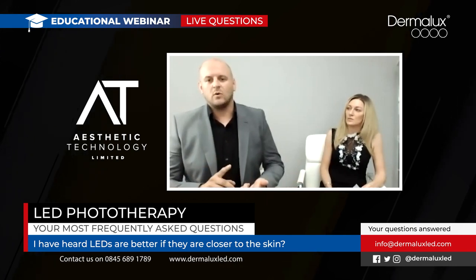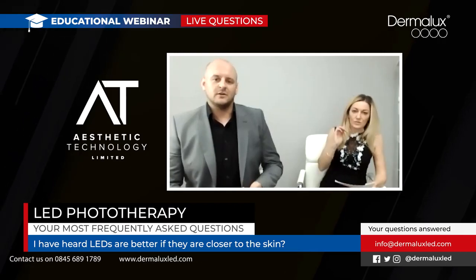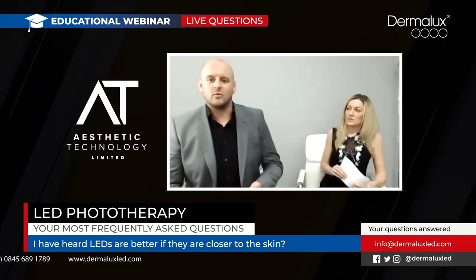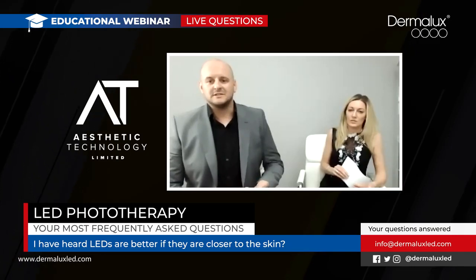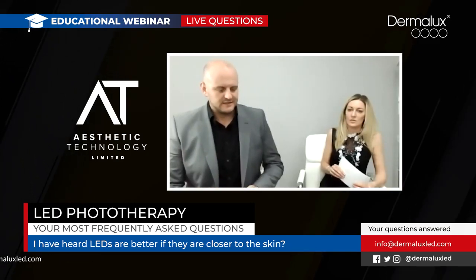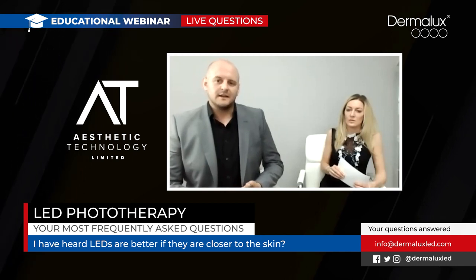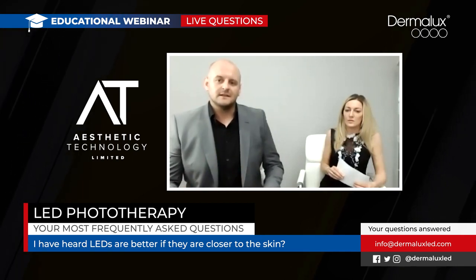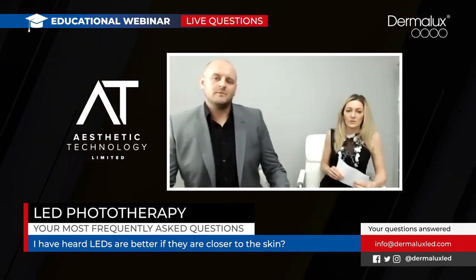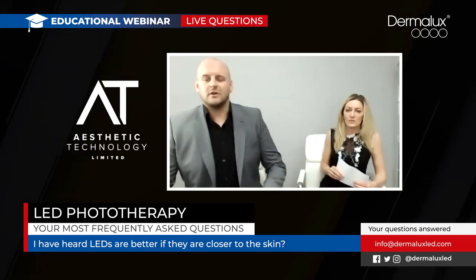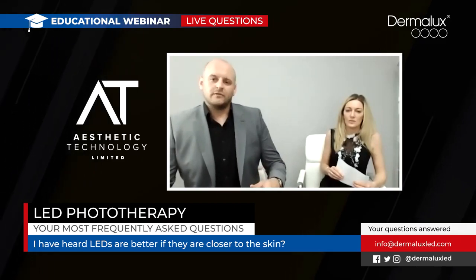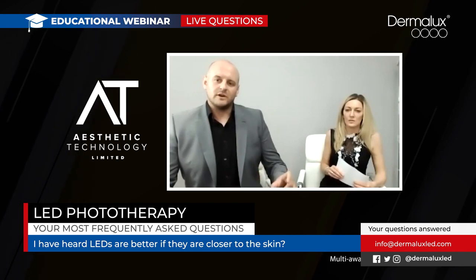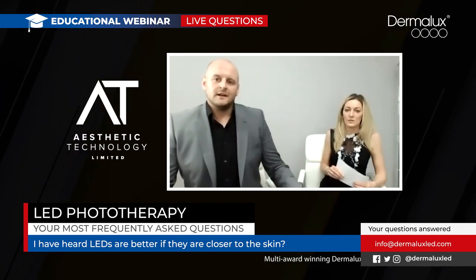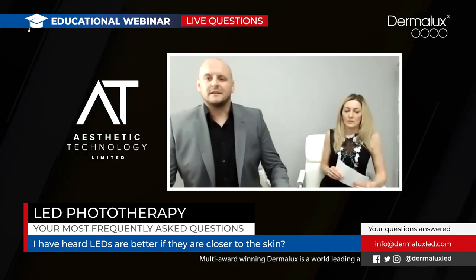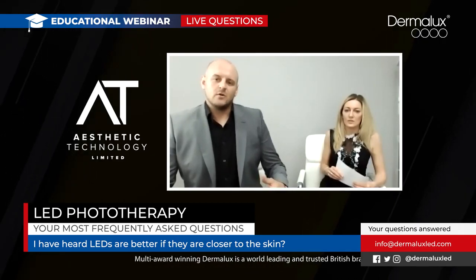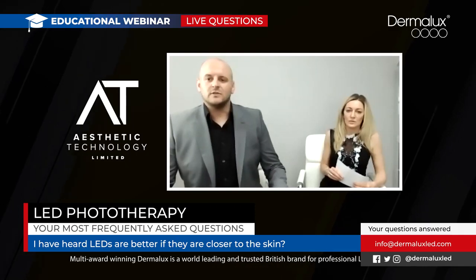What you need to assess is what LED is actually in the mask. Just because it's close to the skin doesn't mean it's more powerful than an LED that's further away. And as I mentioned earlier in the presentation, there is a guideline that stipulates what optical power is being emitted from the device. The risk classification that goes with medical devices runs from risk group 0 through to risk group 3, depending on the overall optical power emitted. Now, a quick indicator: if a mask is a medically approved device and there's no optical radiation labeling on it, typically it would fall into the lowest category.